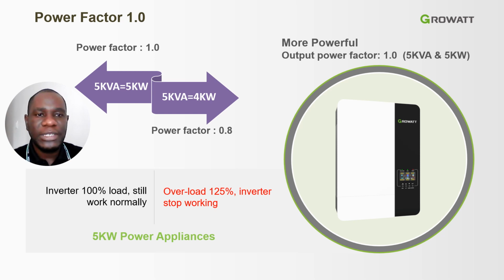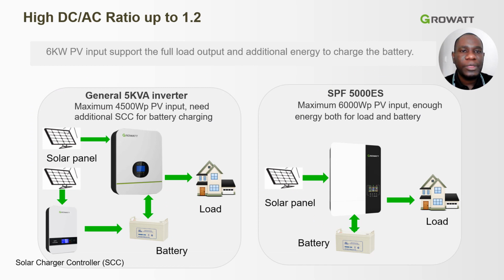Then one of the most important advantages is you can overload this inverter, which means that if you have 100% load, this inverter will still function normally. But if you overload this inverter to 125%, then the inverter stops working. It also has a high DC to AC ratio which goes up to 1.2, one of the most important advantages. This is generally the measure of the efficiency of the inverter, that is, the conversion of your DC to AC usable power from the inverter.